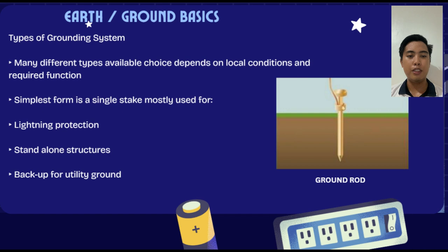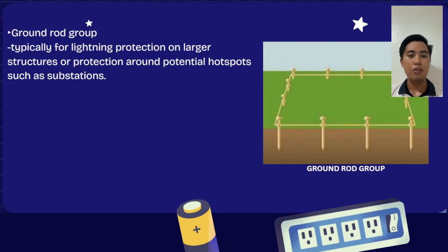So, the simplest form, a single electrode, is mostly used for: first, lightning protection, which safely channels lightning into the earth to protect structures. Second, standalone structures, to provide independent grounding for isolated buildings or systems. Third, backup for the utility ground, which serves as an extra path if the main utility ground fails. The last is ground rod groups, typically for lightning protection on large structures and protection around potential hotspots such as substations.